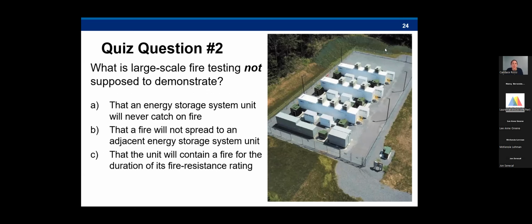All right, it seems we have a consensus with A, and you are correct. Large-scale fire testing is not supposed to demonstrate that a system will never catch fire, but rather to show that the fire will be contained as necessary. And this is also a 20 megawatt system that was installed in Stillwater, New York, just to give you an idea of what these look like throughout the state.